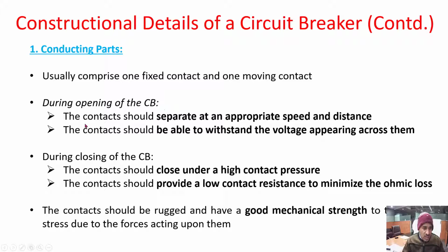During opening of the circuit breakers, the contacts should separate at an appropriate speed and distance. See, it should be fast enough to quench the arc. The distance also should be sufficient to quench the arc. So therefore, the contacts should separate at an appropriate speed and distance. That is very, very important. And the contacts should be able to withstand the voltage appearing across them while opening. Whatever voltage appears, they should withstand.